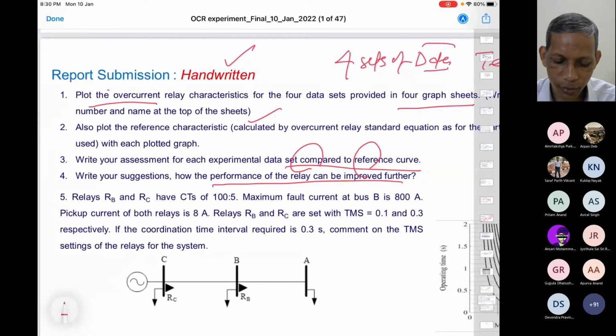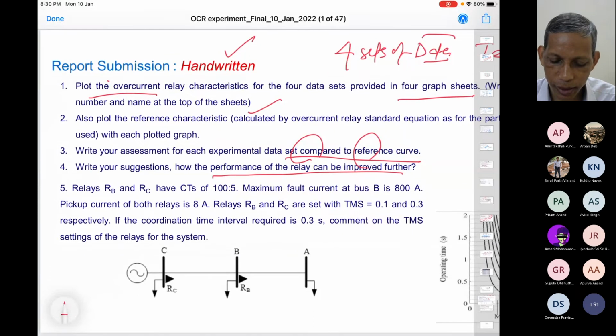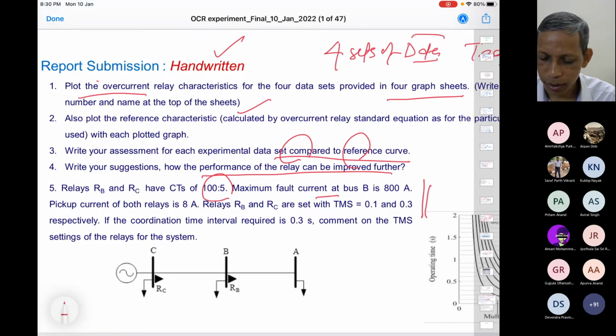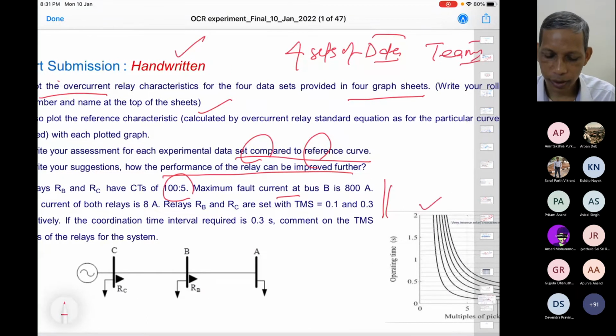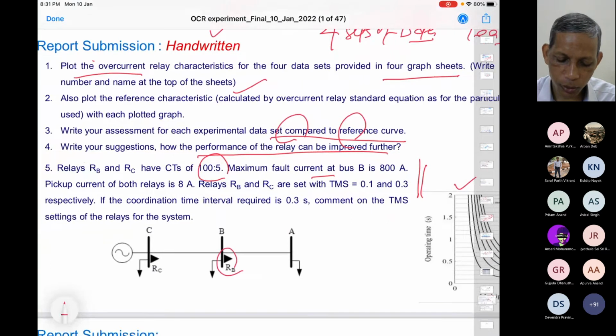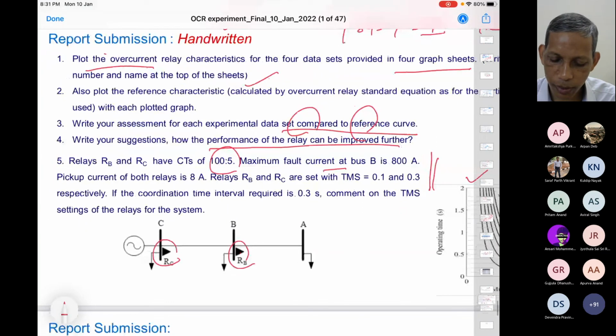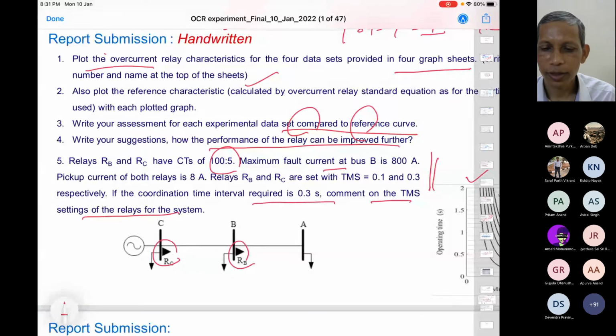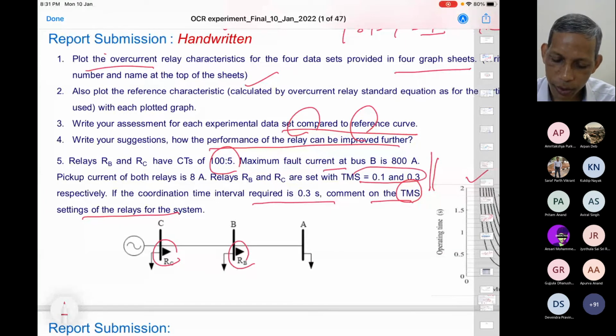The fifth point: relays RB and RC are 100:5. Maximum fault current at bus B, all data are given like what we have seen in the earlier example, and the corresponding curve is also given. So then you have to go for the corresponding calculation. If the coordination time interval at point C is given, comment on the TMS setting of the relay system. You should only talk about the TMS setting which is there. Is it proper? Not proper? Is it satisfying the requirement of coordination or not? That you have to tell.